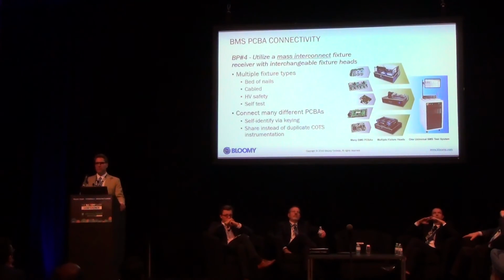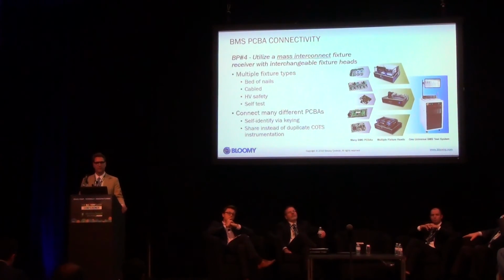So the connectivity, best practice number 4, is to utilize a mass interconnect fixture receiver with interchangeable fixture heads. We go off the shelf with this approach as well. At Bloomy, in our BMS manufacturing test platform, we use Virginia Panel mass interconnects. There are other vendors including Mac Panel, and these systems are great. What they do is allow you to connect any test fixture to the base test rack and all of the instruments in it, which makes that base rack very flexible and reusable for many different PCBAs under test.